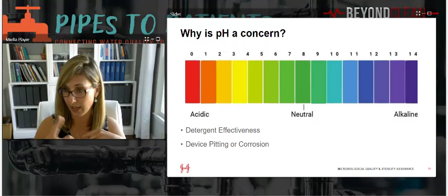And then you'll hear a lot about pH. Having an incorrect pH of your water really can affect the performance of the cleaning agent or detergent you're using, especially enzymatic detergents, because those enzymes are designed to work at a certain pH range. If your water quality doesn't deliver the right pH range, it can inhibit their performance, meaning you're not going to get the cleaning expectation you thought you'd get. In addition, water with an aggressive pH, either too acidic or too alkaline, can also damage the device material and result in that pitting and corrosion I showed you in the previous picture.